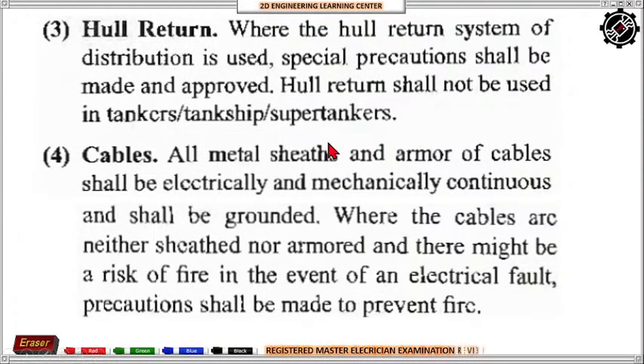But hindi siya pwedeng gamitin if the type of boat or ship is a tanker, tank ships, or super tankers. Cables, all metal sheaths and armor of cables shall be electrically and mechanically continuous and shall be grounded. So where the cables are neither sheathed nor armored, and there might be a risk of fire in the event of electrical fault, precaution shall be made to prevent fires.